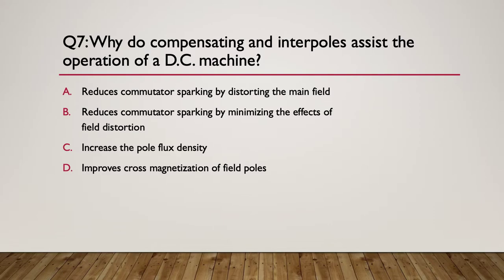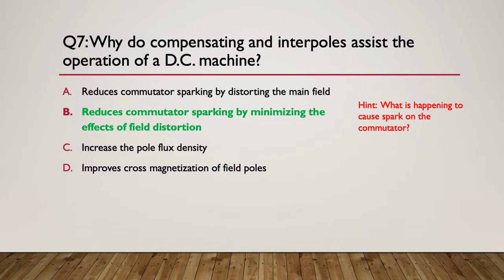Question seven: why do compensating and interpoles assist the operation of a DC machine? These are the extra field windings we put into a machine. A, reduce commutator sparking by distorting the main field. B, reduce commutator sparking by minimising the effects of field distortion. C, they increase the pole flux density. D, they improve the cross-magnetisation of the poles. Hint: what is causing sparking on the commutator? The answer is B - they reduce commutator sparking by minimising the effects of field distortion, making the field so strong that we end up with very little field distortion and therefore very little sparking.